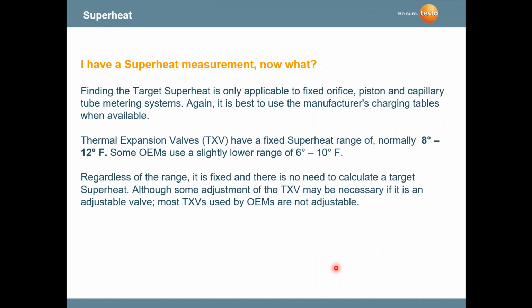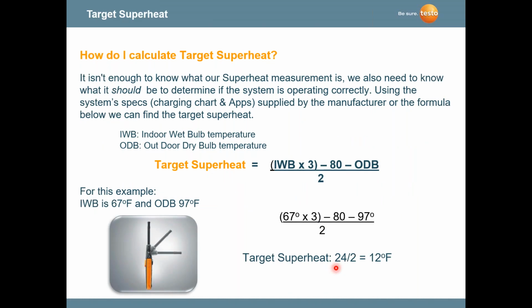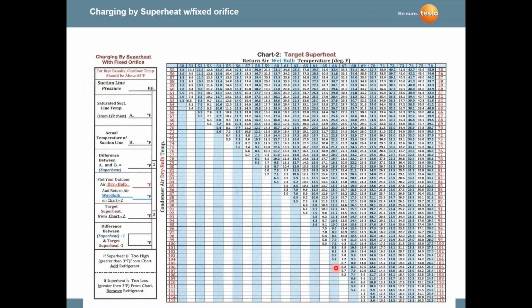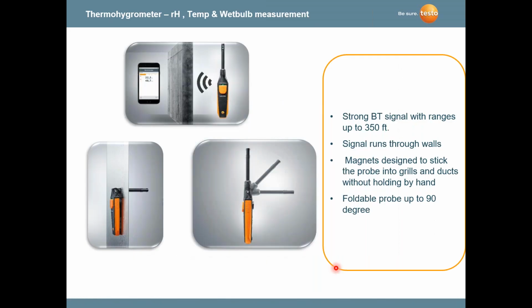Typically with superheat using TXVs, the nominal or normal range of a TXV for superheat is 8 to 12 degrees Fahrenheit. We used to calculate this way back. Maybe some of you on board can recognize the formula for getting the targeted superheat. Maybe you used charts before, looking at the return air wet bulb temperature and the outdoor temperature.